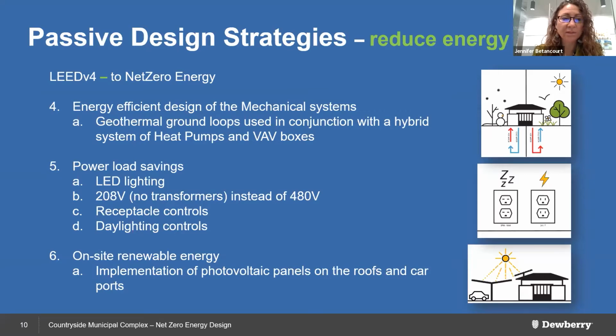On the power loading side, we utilized all LED lighting. We were able to eliminate transformers by not bringing in 480, we brought in 208 instead. We also had receptacle controls, daylighting controls, and renewable energy on site for energy production to bring us to net zero.